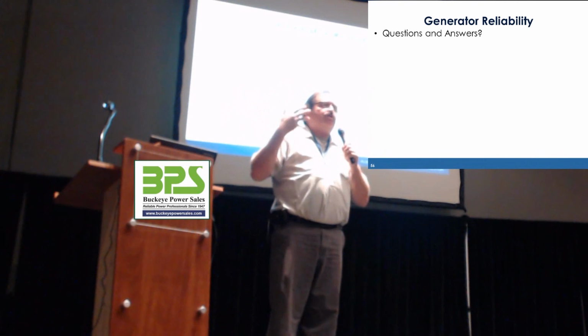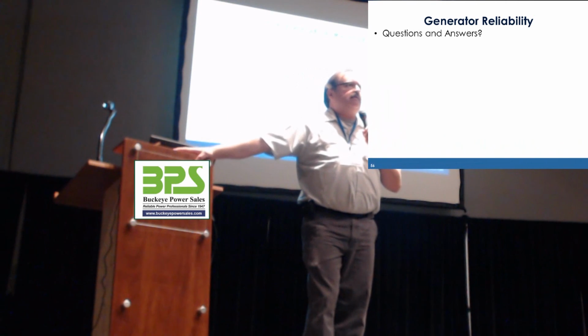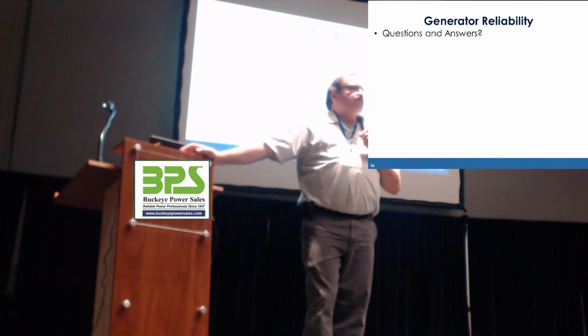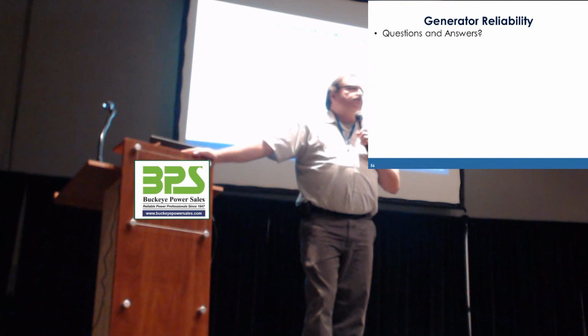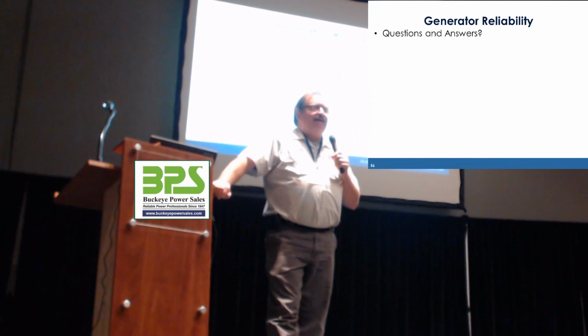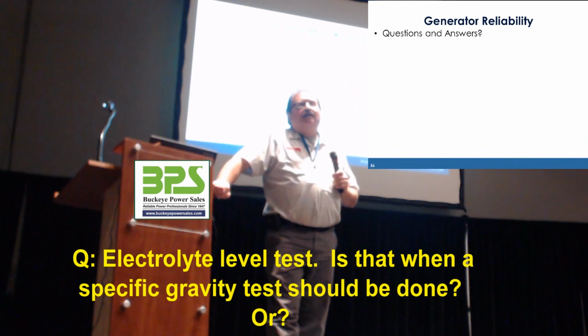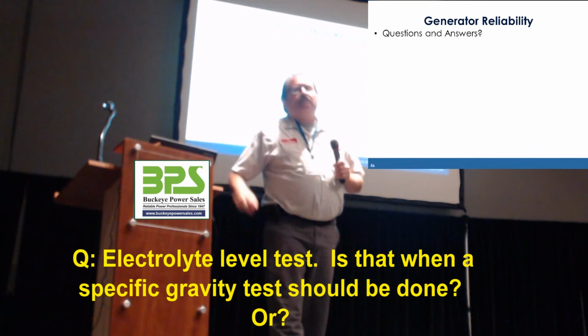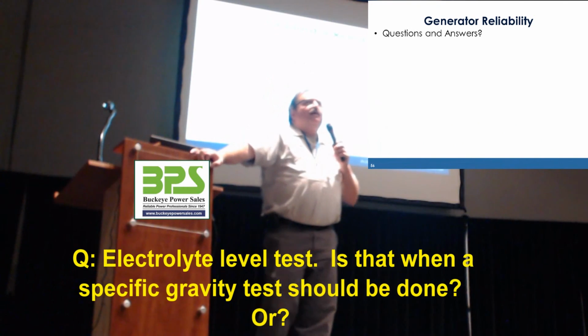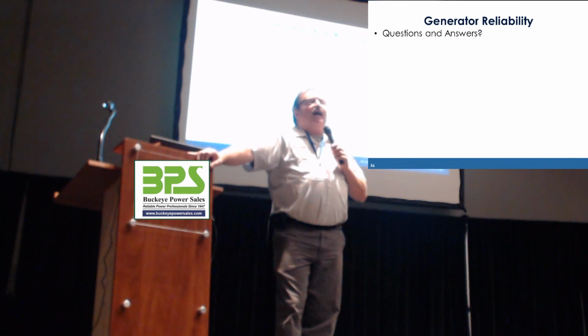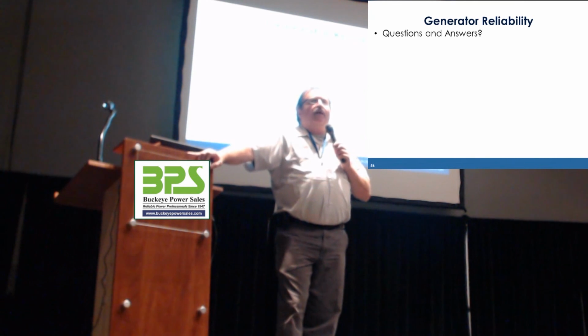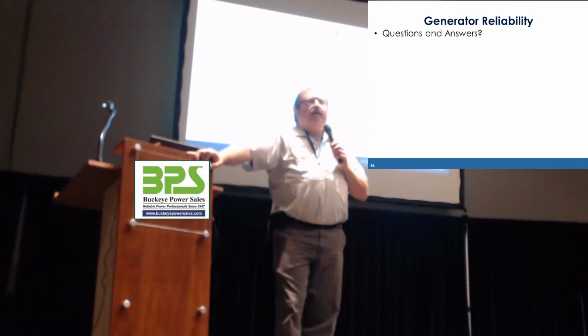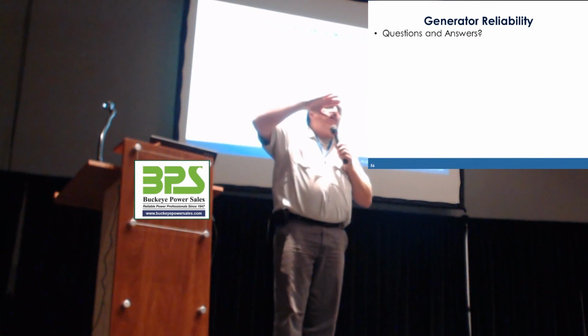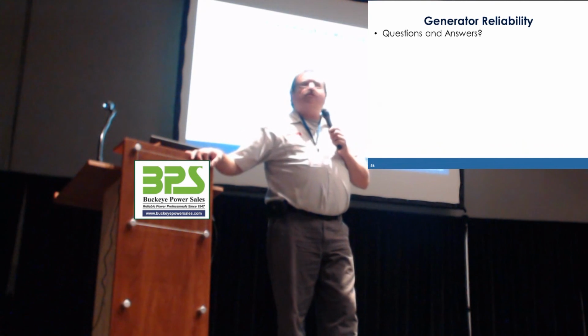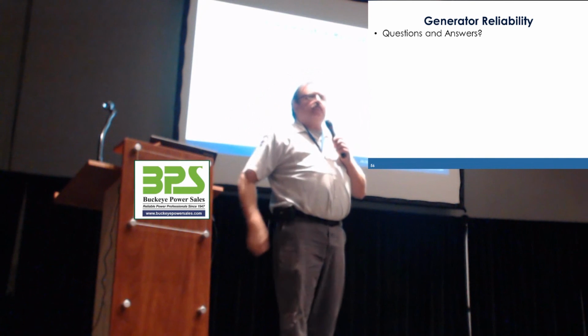I didn't mention this because it should be common sense, but we all know that common sense isn't. When you're checking the electrolyte or doing anything with the battery, no smoking. Ideally, that's really something that as an operator, you're not required to do. The operator maintenance just requires you to look at the level. The maintenance side requires the specific gravity test. If you do have to top off the fluid in the battery, only use distilled water. Never add acid to a battery that's already charged up.